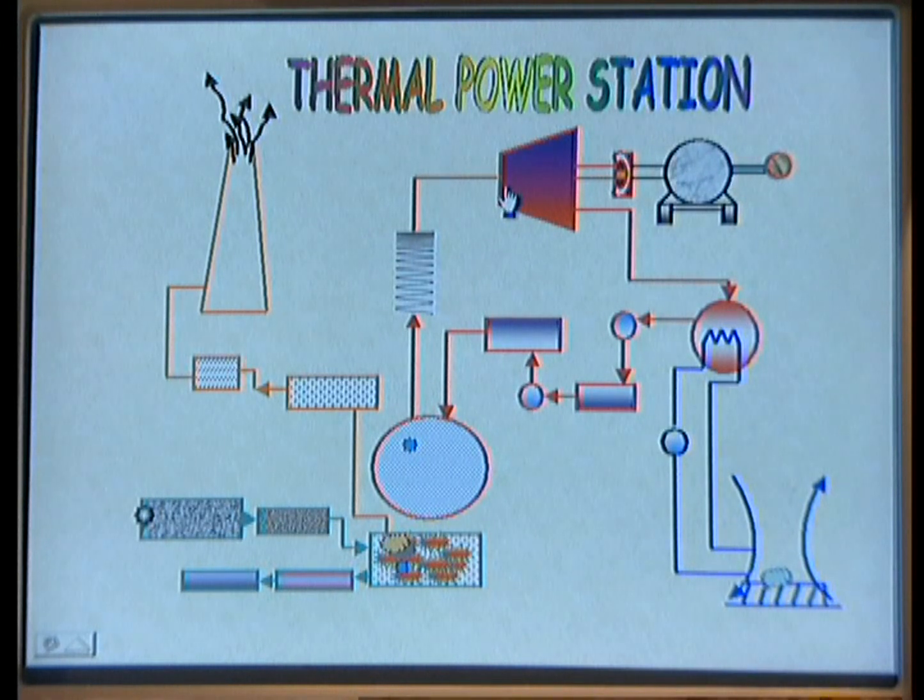After passing through a number of fixed and moving blades, the turbine will rotate. It is mechanically coupled to our generator. Once the generator rotor rotates, as per Faraday's laws of electromagnetic induction, EMF is induced. This voltage may be nearly in the 11 kV to 33 kV range, and we require some DC excitation, that is supplied by the exciter, a DC compound generator, with a voltage of 115 to 230 volts DC supply.